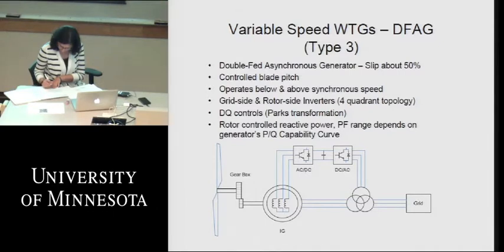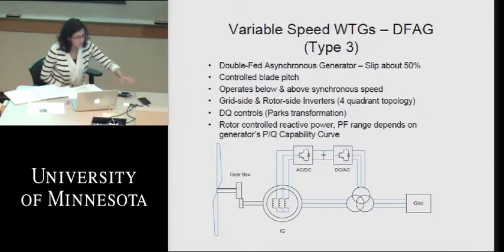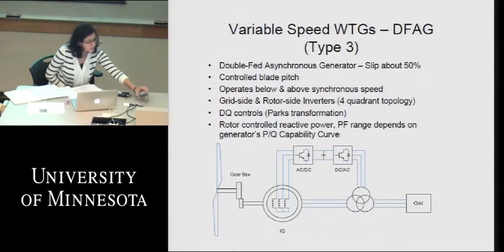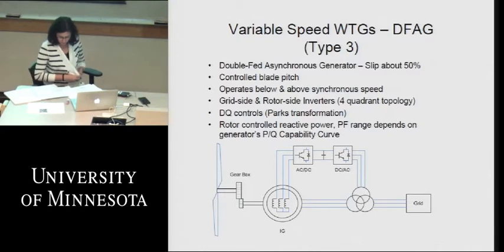So Type 1, we had no slip, so any change in the wind speed is automatically seen by the generator, and so automatically seen by the power output. But with this slip control, we can actually soften the impact, and even though there are wind changes, we can store that excess energy when the wind drives too hard, like I said before, and release that energy into the grid when the wind dies down. And it's a very nice system for providing very flat and very predictable power output from the generator. Of course, we needed to have controllable pitched blades. For this, the variable speed curve comes from the blades being changed, so we can change the speed of the actual mechanical rotor of the wind turbine. But we follow that with this slip control to give a very seamless output of power to the grid.